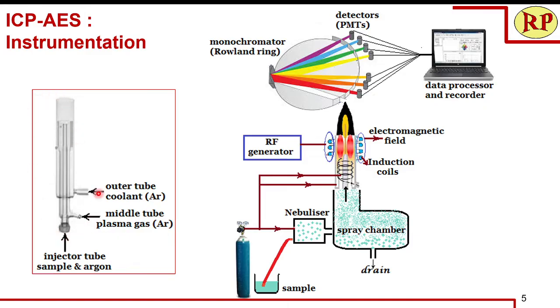The plasma torch is mainly made of quartz glass or ceramic. It has three concentric tubes. Through the center tube — also called the injector tube — the sample and argon gas are injected. Through the middle tube, argon gas is supplied to create the plasma flame. The outer tube supplies argon gas that acts as a coolant, protecting the quartz tube from the very high temperature at the center.